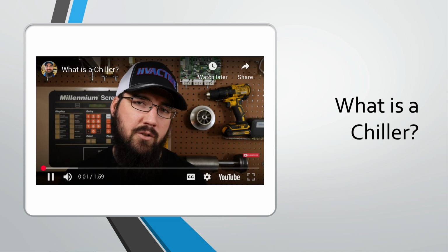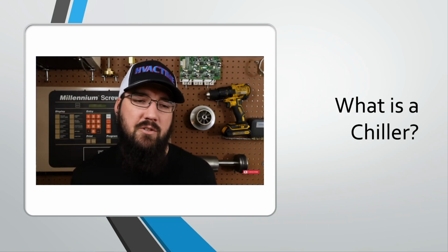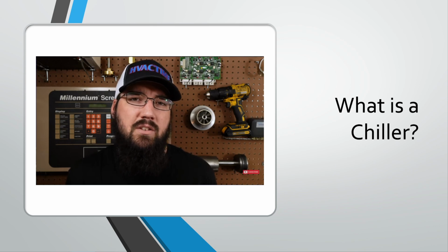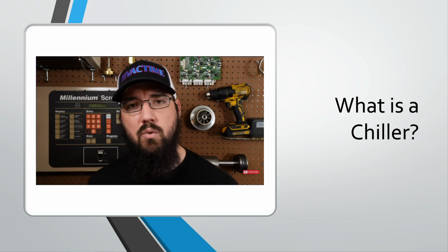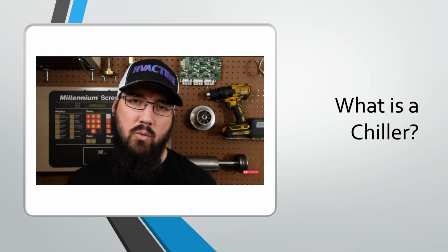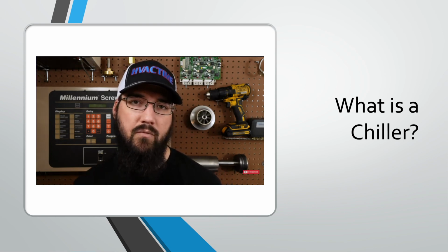You hear the term chiller thrown around plenty, and you have to ask yourself the question at some point, what really defines a chiller from just a regular air conditioner? Like why is it special? What is that? The short answer is it's a hydronic cooling machine, meaning the evaporator itself uses a hydronic evaporator. Now, hydronic is using water. That is, hydro is the use of water through the evaporator, and we're going to cool the water down to go cool the space. But a chiller specifically, whether it be water or brine or a glycol solution, either way, it's a fluid. We're cooling a fluid versus air.